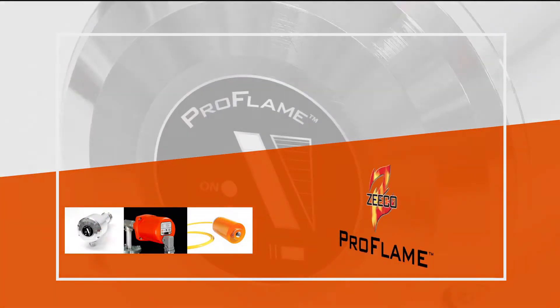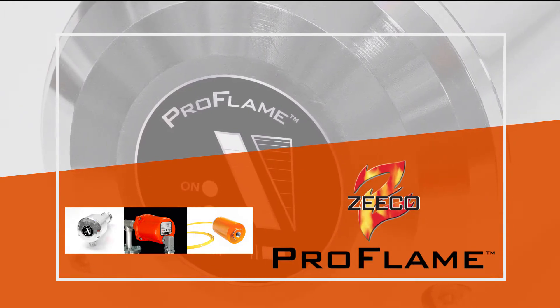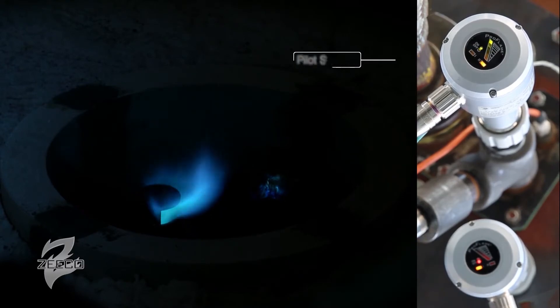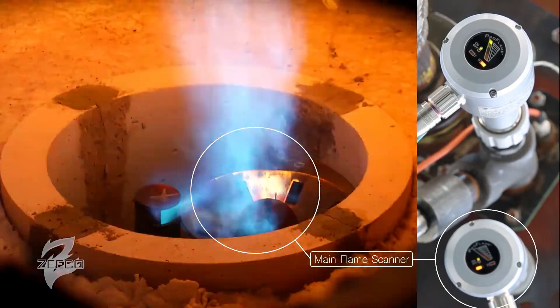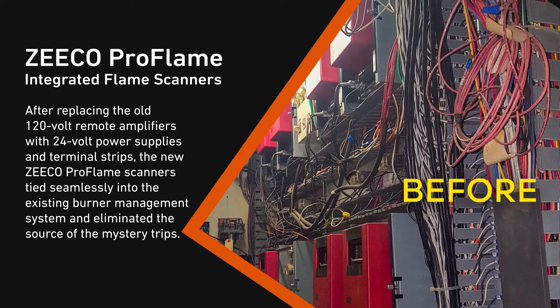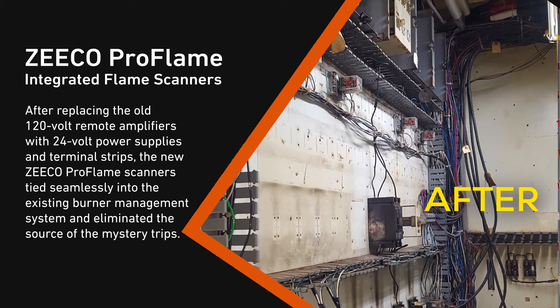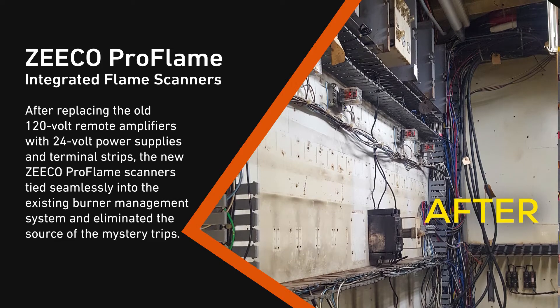Zeeco replaced the existing flame scanners and flame signal amplifiers with Zeeco Pro Flame Scanners, a technology that houses a flame signal amplifier and a signal strength meter in a single, compact unit with an easy-to-read LED display. After replacing the old 120-volt remote amplifiers with 24-volt power supplies and terminal strips, the new Zeeco Pro Flame Scanners tied seamlessly into the existing burner management system and eliminated the source of the mystery trips.